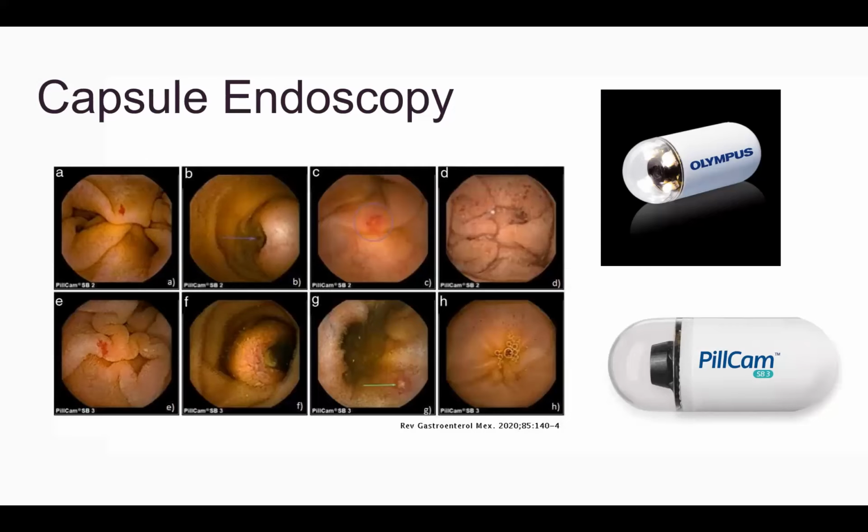So a capsule endoscope is a small device measuring about 18 millimeters in length and about 9 millimeters in width, with a couple of batteries in it, a wireless transmitter, some LED lights, and a small camera. It takes frames at a rate of about 2 to 6 per second, and the patient swallows it, and then you get a video of the small intestine given back to you on a data recorder that you upload to a specific bit of software.